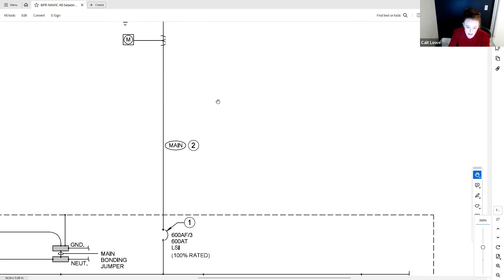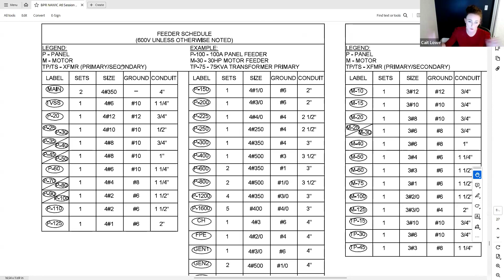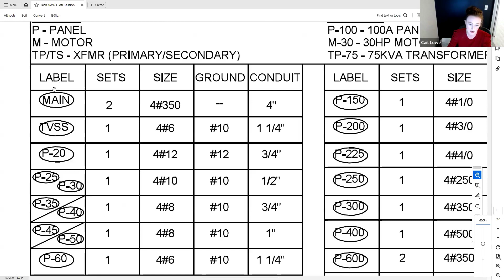Then I'm going to see these little designations - this is main, and I've got a schedule here, it's a feeder schedule. So your feed is your main line, okay, the main source of power. Then you've got little branch-offs based on where your lights are. So it's telling me this is main, 4-inch conduit.